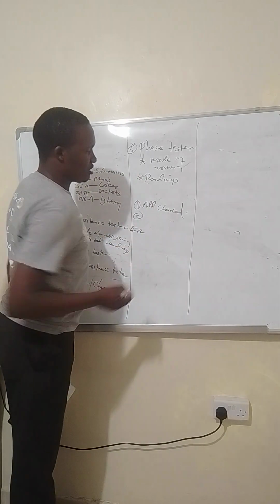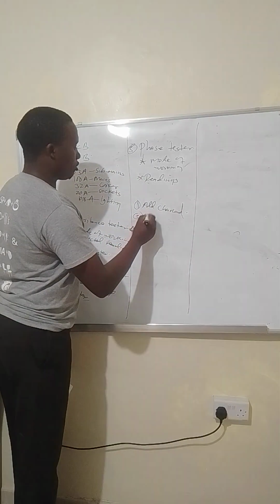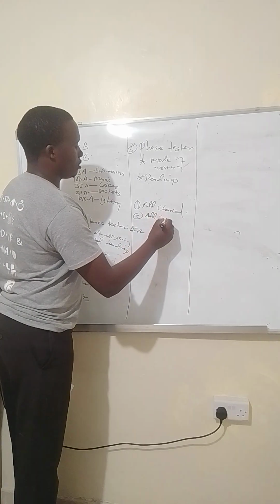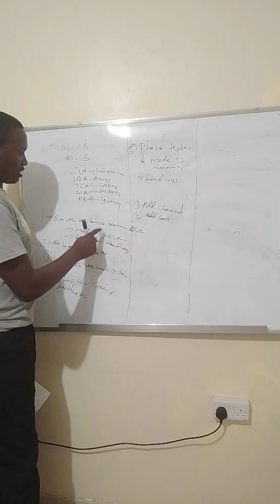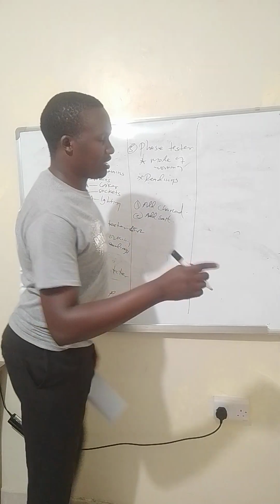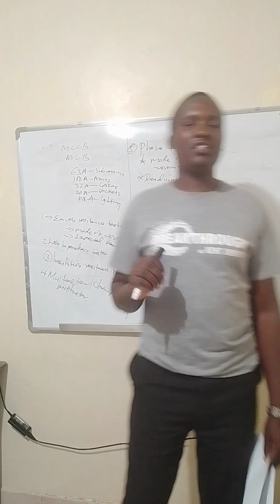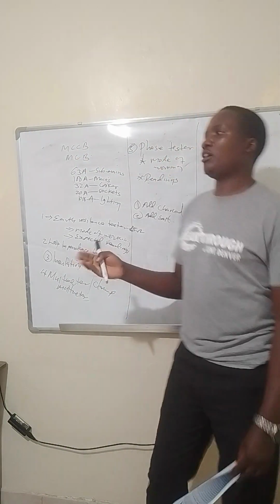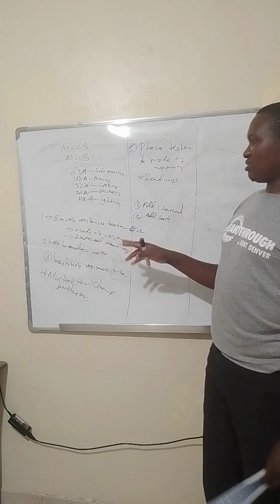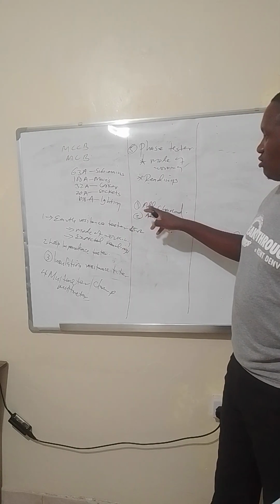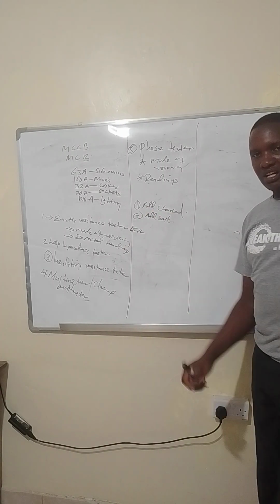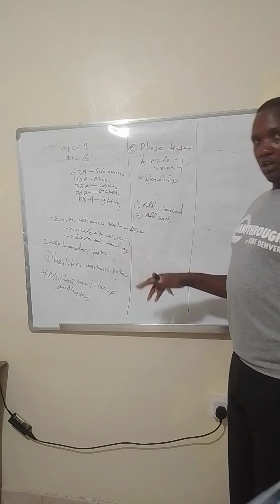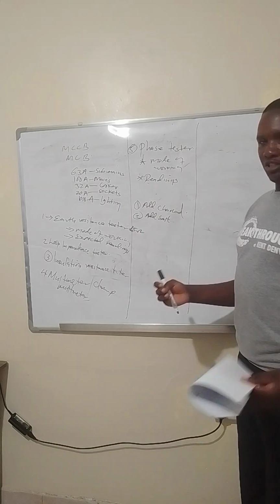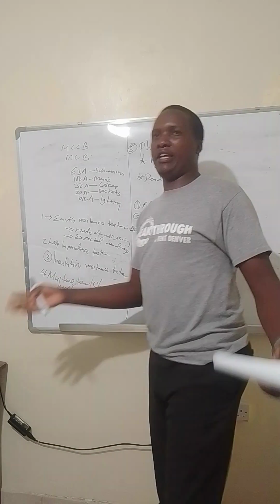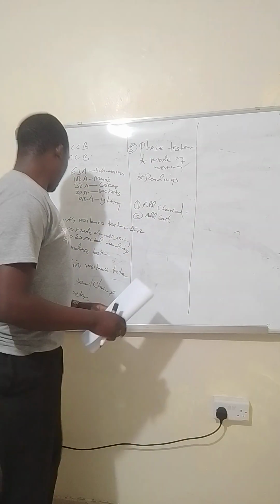If the resistance is very high, add salt until this resistance comes to less than 5 ohms. That is the correct reading you need to get after you have done your test using an earth resistance tester. If the resistivity is too high, add charcoal to the mother ground, or salt, or both, depending on your area where you are doing earthing.